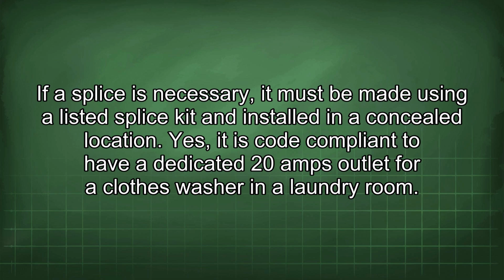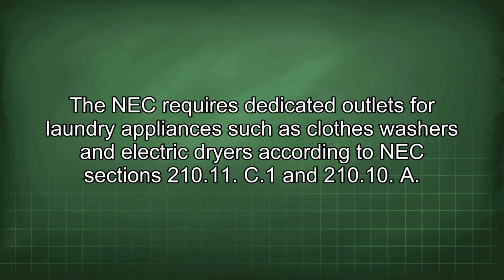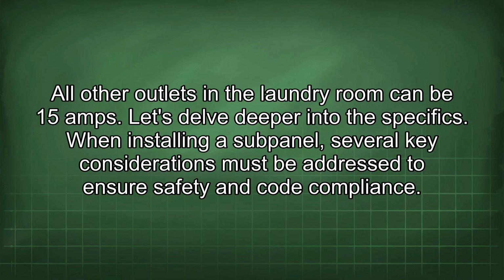Yes, it is code compliant to have a dedicated 20 amp outlet for a clothes washer in a laundry room. The NEC requires dedicated outlets for laundry appliances such as clothes washers and electric dryers, according to NEC sections 210.11(C)(1) and 210.10. All other outlets in the laundry room can be 15 amps. Let's delve deeper into the specifics.